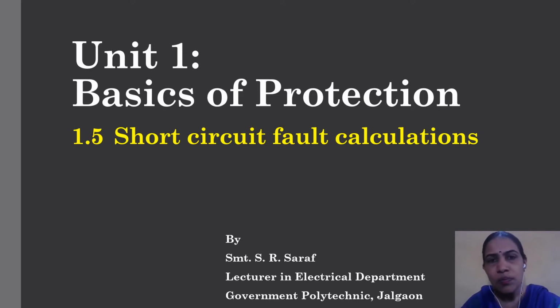Friends, in a power system, while designing an electrical power protection system, it is very important to select the proper current rating of circuit breakers, relays, CTs, and isolators, and for that, short circuit fault current calculation is very important. The circuit breaker should be capable of breaking and making the current as per its ratings, and it should also have a rated short time capacity.